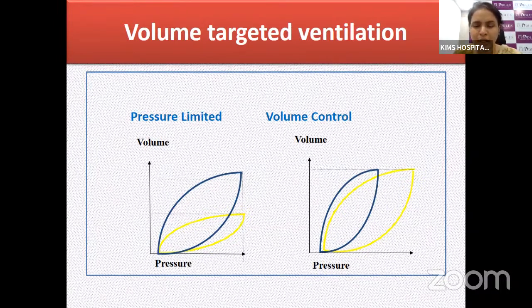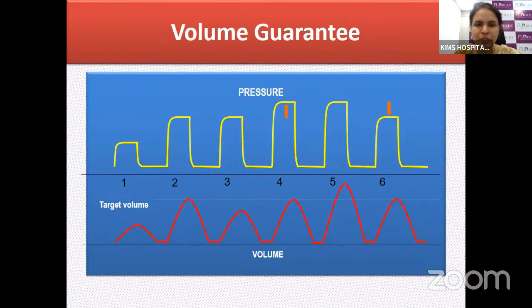This has been found to be an advantageous strategy because it has been realized that volume trauma is more damaging to the lung than pressure trauma or barotrauma. So this is an example of the tidal volume. The second loop represents the volume scalar in volume guarantee mode of ventilation, wherein based on the tidal volume reached, the peak pressure of the next breath is changed. So for example, after the second breath, wherein tidal volume was exactly reached, you can see that the same peak pressure was delivered for the next breath. Whereas when the tidal volume dropped below the target volume in the third breath, the PIP for the subsequent breath was increased in the fourth breath.